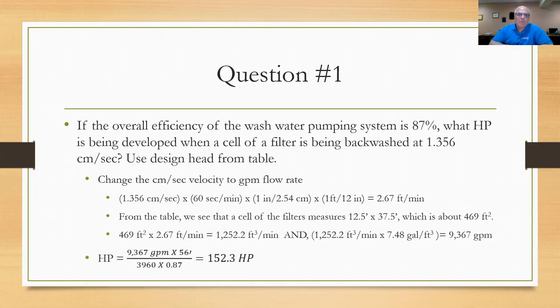So now I can work the horsepower problem. I'll go to the table if necessary and get the formula out, and it says multiply the gallons per minute, which was 9367, times the head, which I found from the table is 56 feet, divided by the 3960 and the efficiency, which was 87 percent according to the problem. And I come up with an answer of 152.3 horsepower. Hope you did well on that.